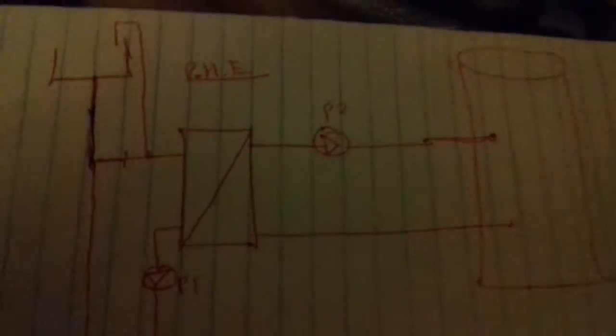And then when we come to the other side of the plate heat exchanger, we need a pump. So I guess we can put that on the return side of things. Here is the return on the plate heat exchanger side, but the flow on the cylinder side is not connected to the right place. So what we can do is leave that valve closed, cap it off, take the pipe off here, and connect that pipe into the buffer tank, either at that point or tee it in there. It's probably fine to go in there if the pipe was run neatly across there.